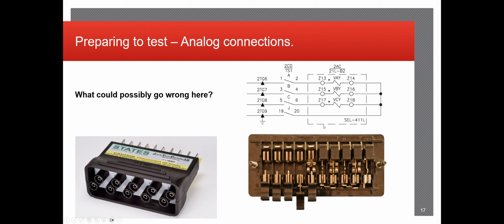Analog connections, what could go wrong here? Again, like we talked about, if you designate your phase incorrectly, you're going to be running into a lot of issues in your testing phase and wondering what's going on, and realizing your C and A phase are flopped or something like that. As well as making sure all the equipment is properly isolated and rated for the voltages and currents that you're actually going to be applying.